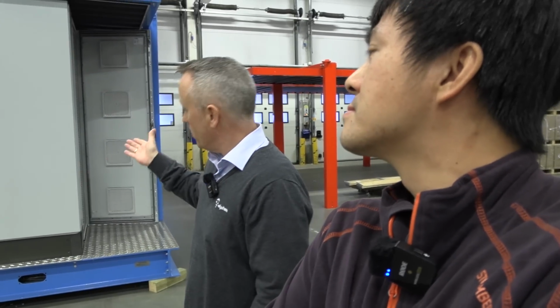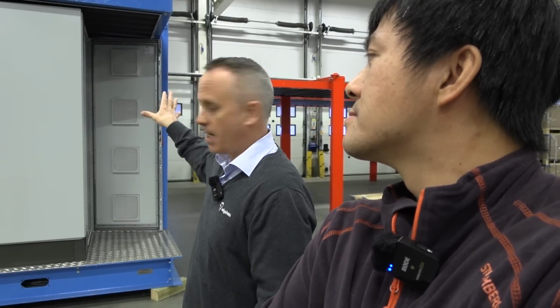We can also reduce the tariff costs in total, because you can use the energy stored in the batteries to feed back to the building. In the morning, especially 7 to 9 o'clock when people are starting their offices, the tariffs, especially in Norway, are very high. But you can use energy from the battery when you're starting the air conditioning or something else. If you do that every day for 250 days a year, it's an enormous amount of money to save. Also, when it comes to solar systems, the unit is perfect because the overproduction from your solar panels can be saved in the battery bank.